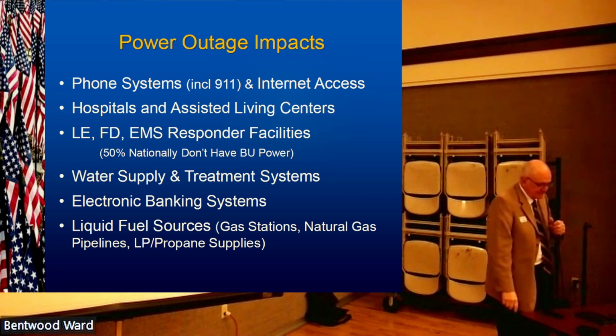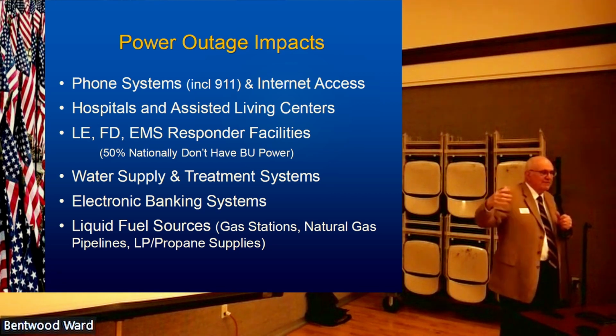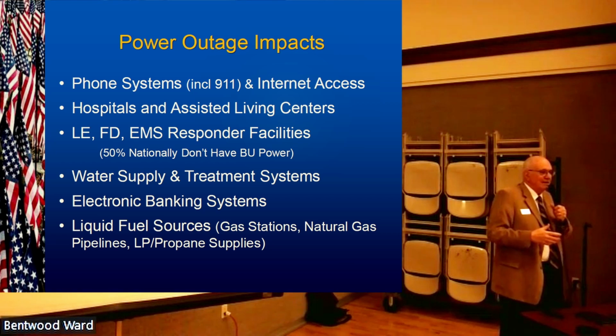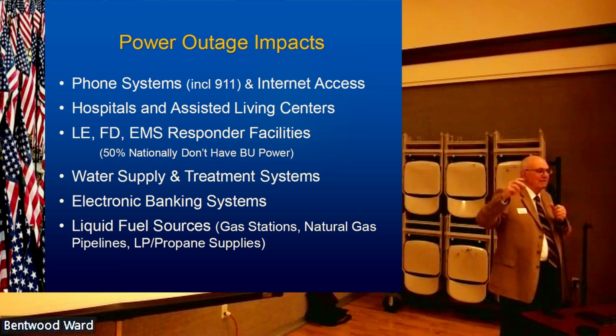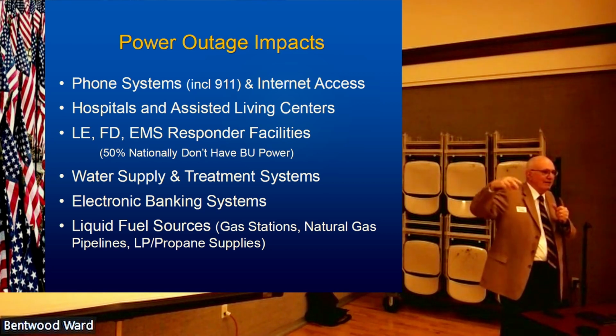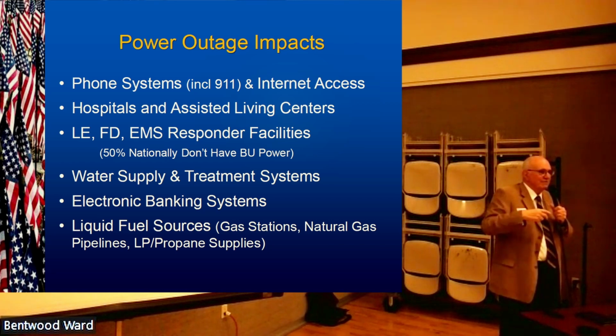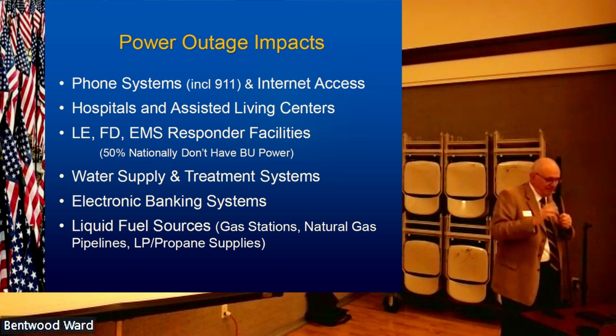Liquid fuel: natural gas needs to be pumped under pressure. It gets that pressure from pumps, which may be fired by natural gas, but most of the time they're powered by electricity. So if there's a power outage, it might shut off the natural gas supply for a given area, and you're depending on your generator to kick on because it's hooked to natural gas -- that won't happen, so just be aware of that.